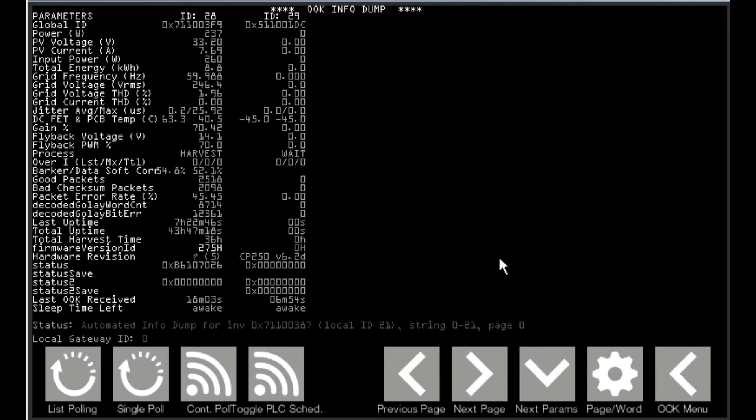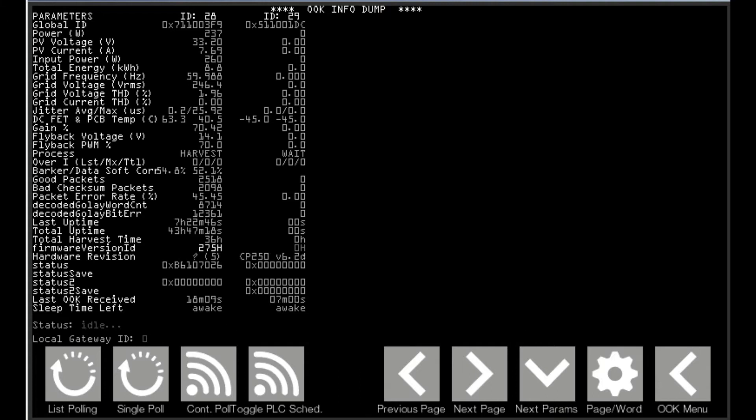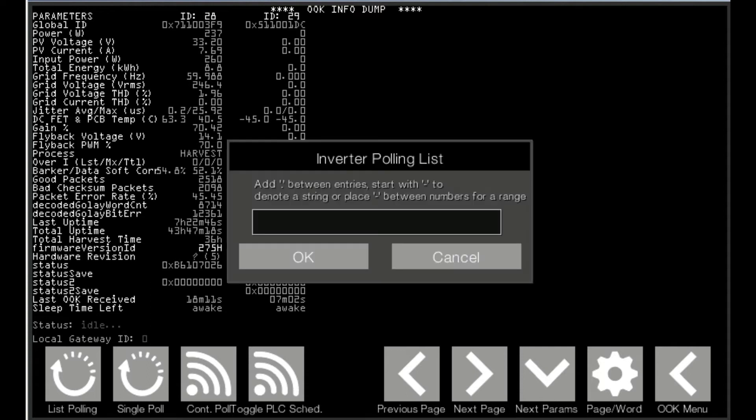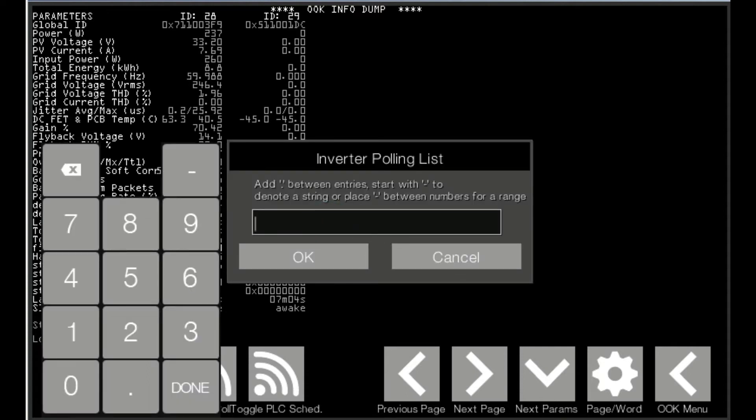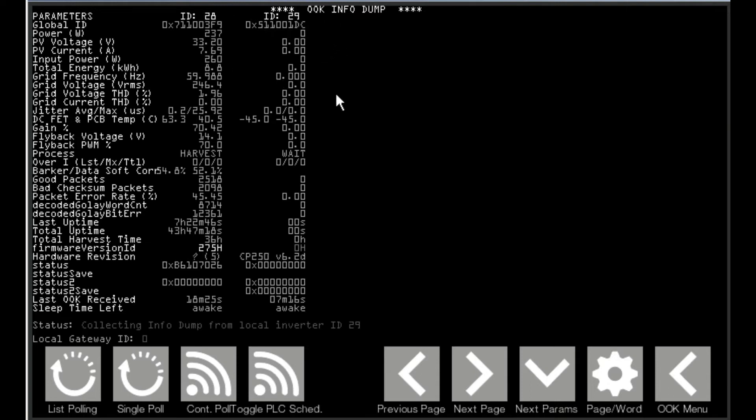If you don't want to wait you can always turn off the scheduler. By hitting toggle PLC schedule. Click list poll. And then enter the local ID of the unit which is here that you want to poll specifically. And get data from that unit directly. So now we're sending a message out. And we can see that we polled that unit and it's powered up and it's harvesting.